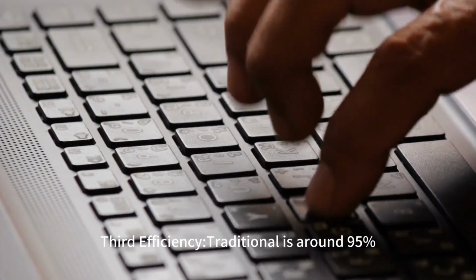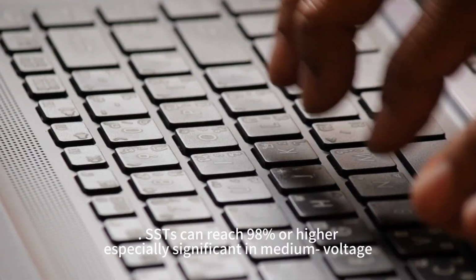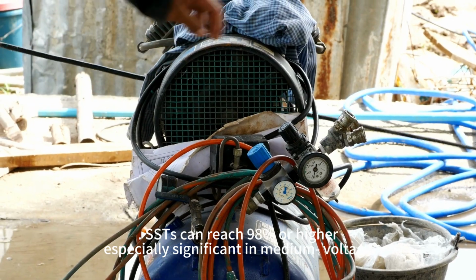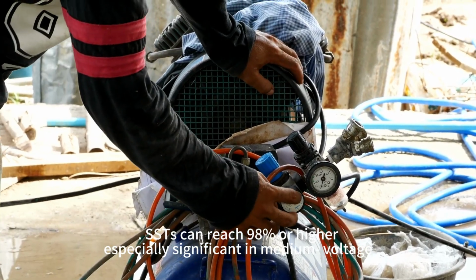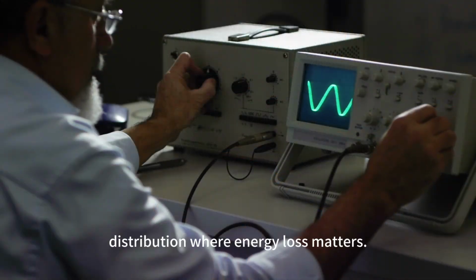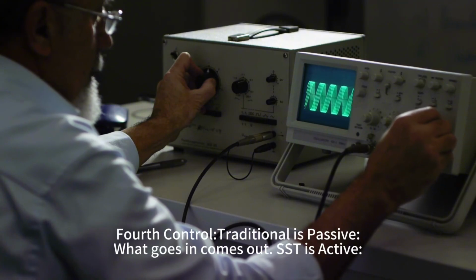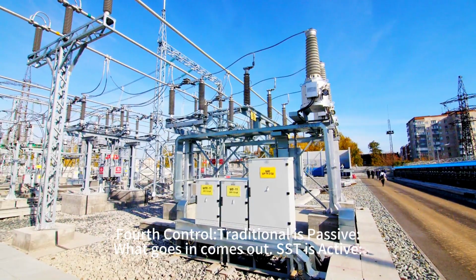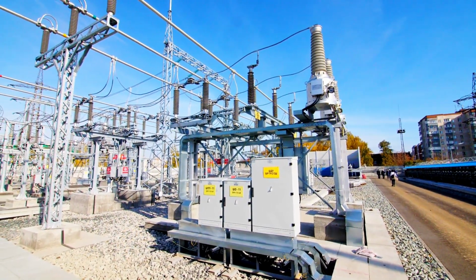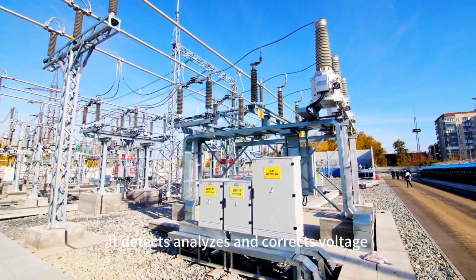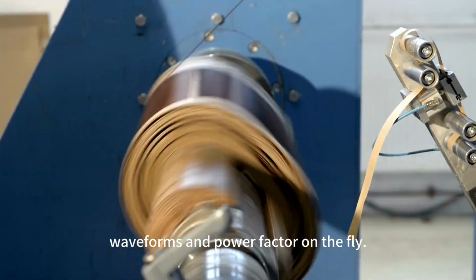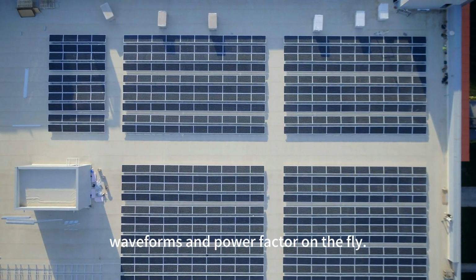traditional is around 95%, SST can reach 98% or higher, especially significant in medium voltage distribution where energy loss matters. Fourth, control: traditional is passive, what goes in comes out. SST is active, it detects, analyzes, and corrects voltage, waveforms, and power factor on the fly.